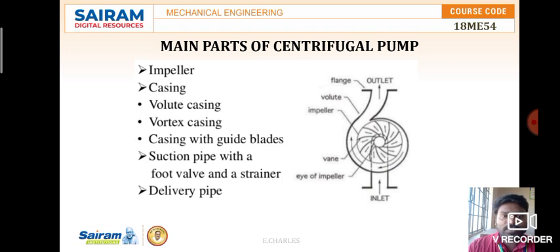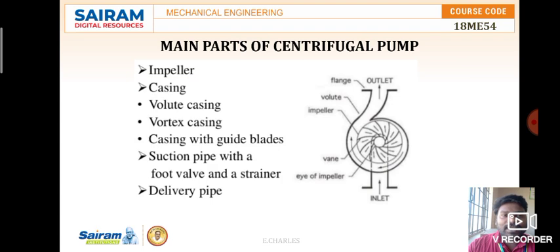The main parts of the centrifugal pump are: impeller, casing (including volute casing, vortex casing, and casing with guide blades), suction pipe with a foot valve and strainer, and delivery pipe. The impeller is the most important part of any pump or turbine. It is mounted on the shaft, with a series of fixed or movable blades forming the rotor assembly, which directly produces the pressure energy of water.